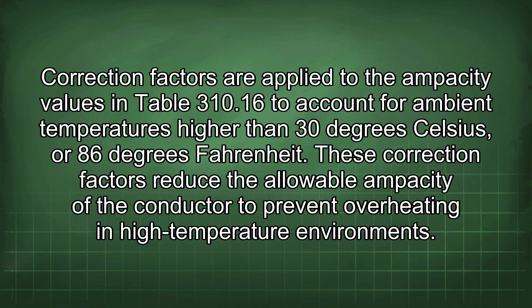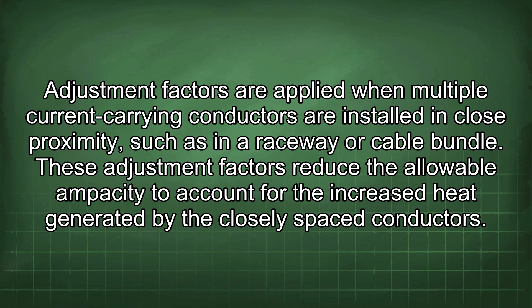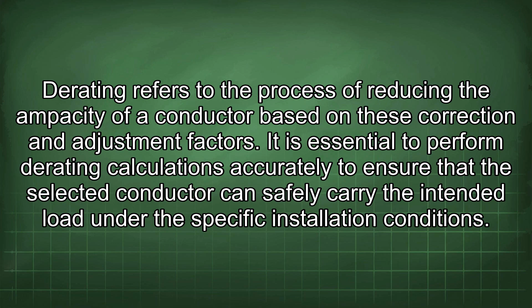Adjustment factors are applied when multiple current-carrying conductors are installed in close proximity, such as in a raceway or cable bundle. These adjustment factors reduce the allowable ampacity to account for the increased heat generated by the closely spaced conductors. Derating refers to the process of reducing the ampacity of a conductor based on these correction and adjustment factors. It is essential to perform derating calculations accurately to ensure that the selected conductor can safely carry the intended load under the specific installation conditions.